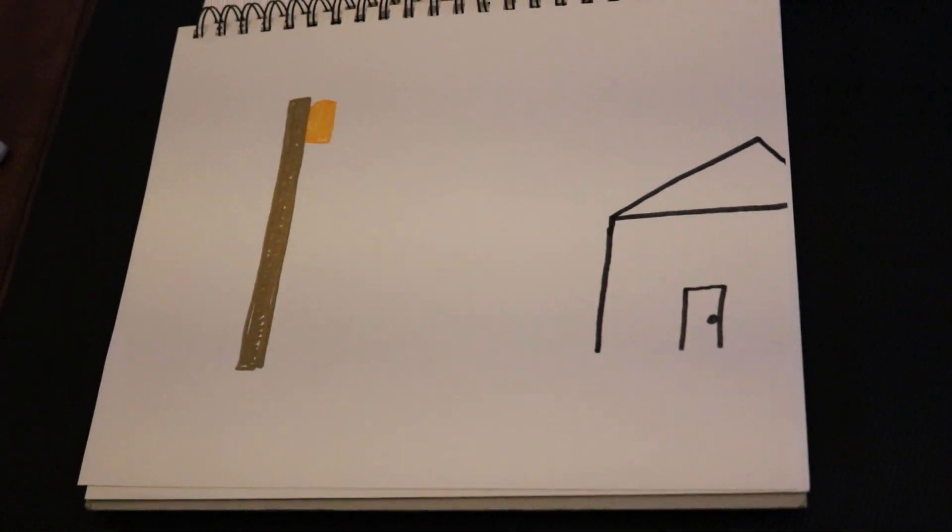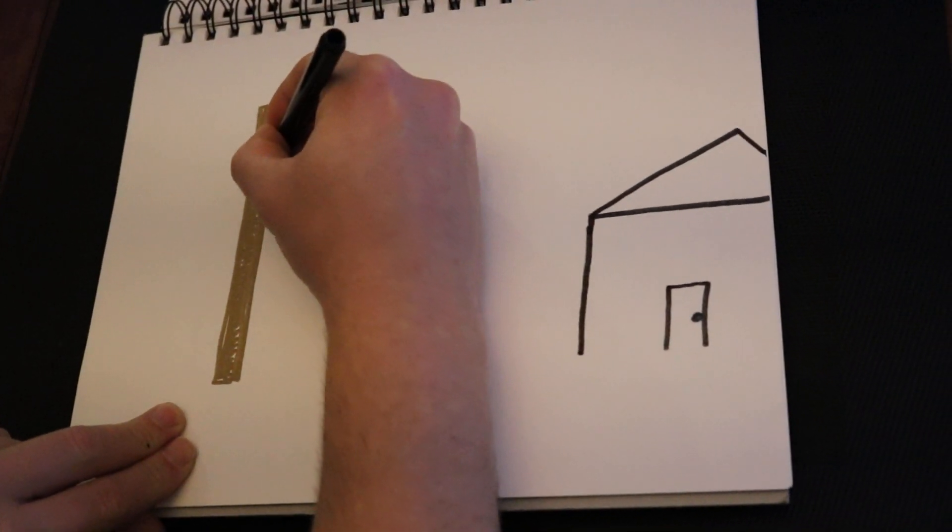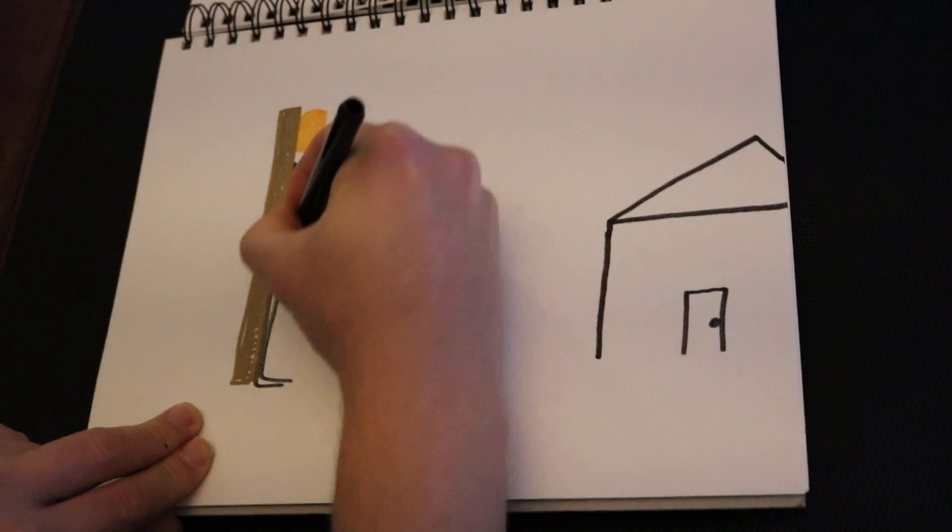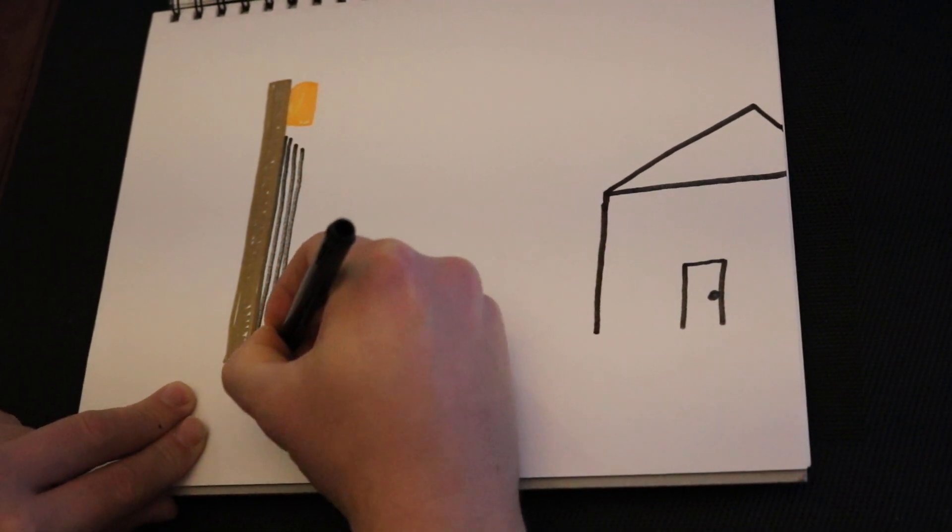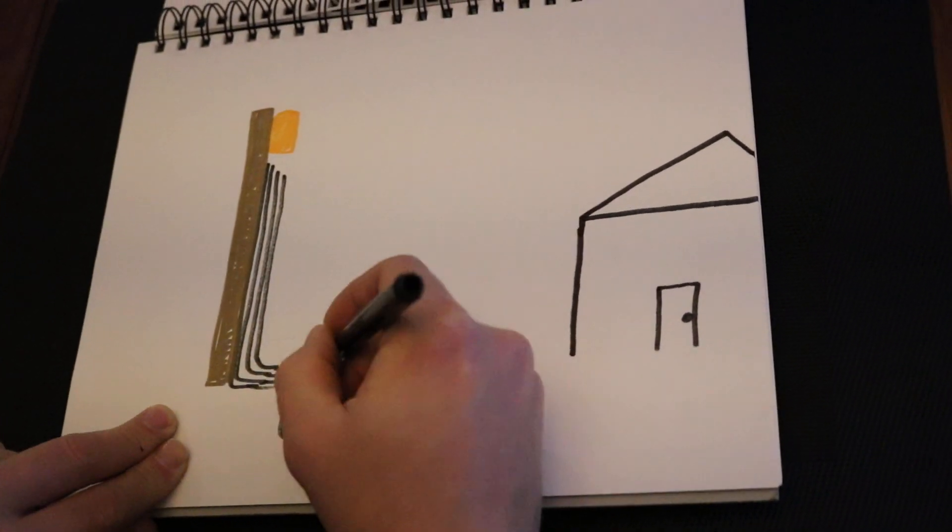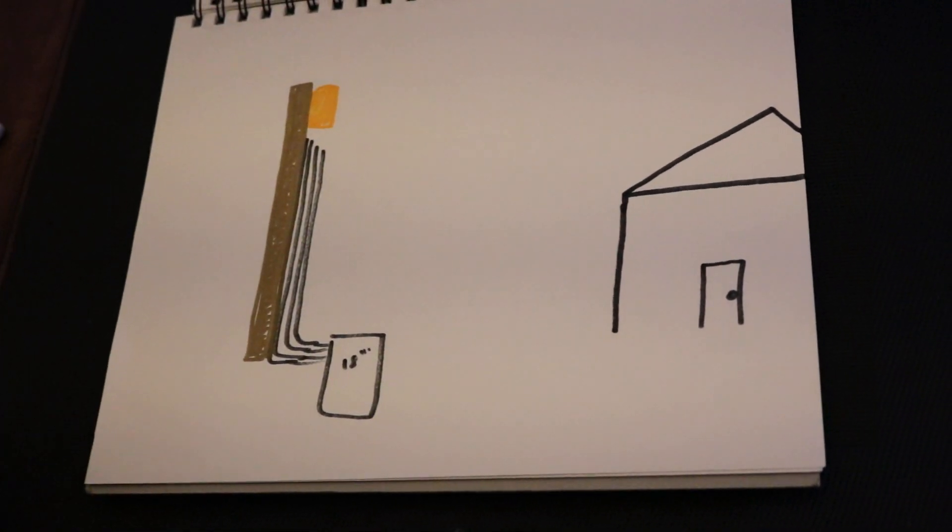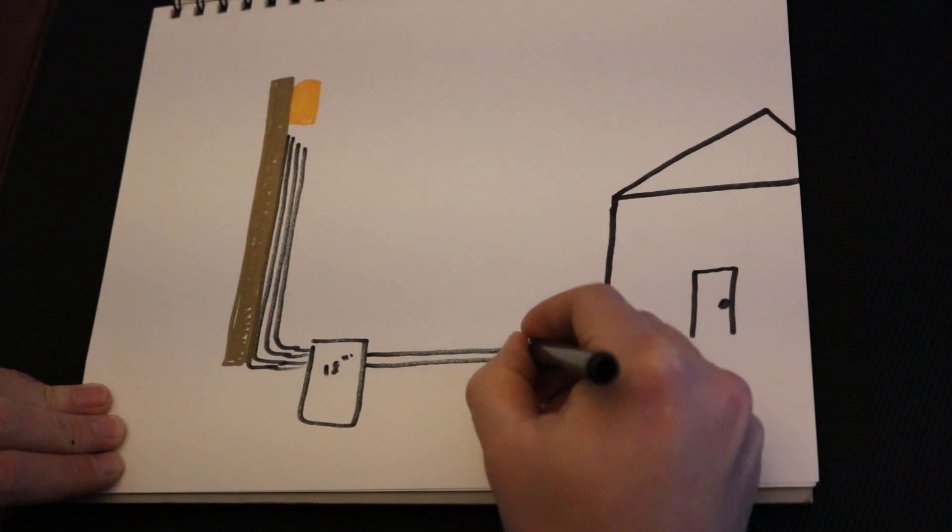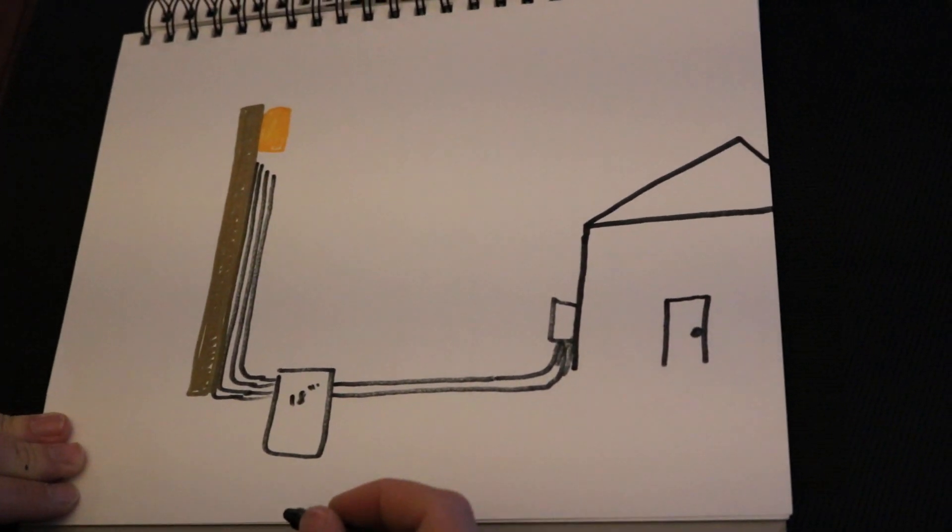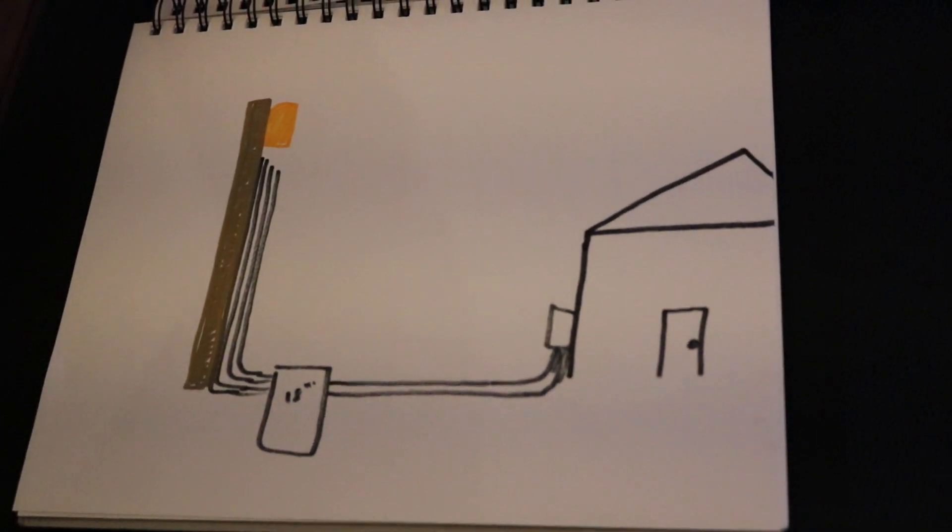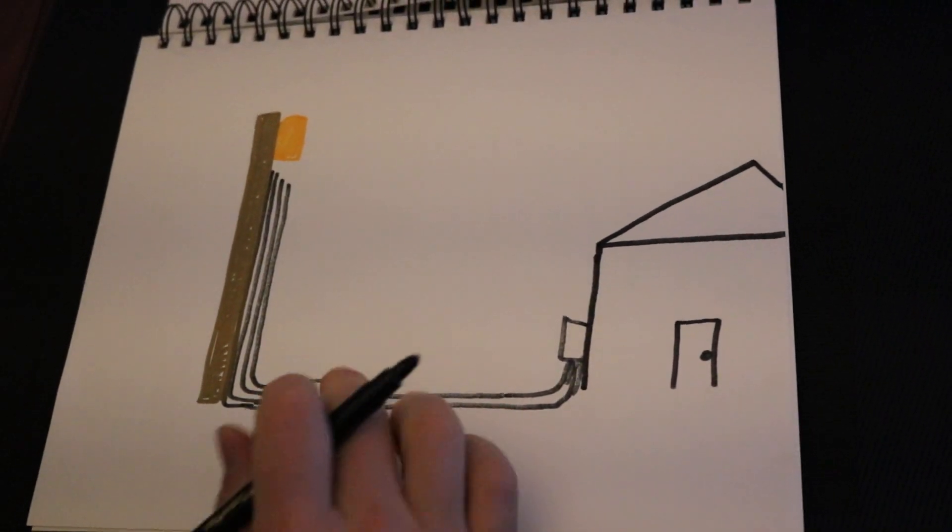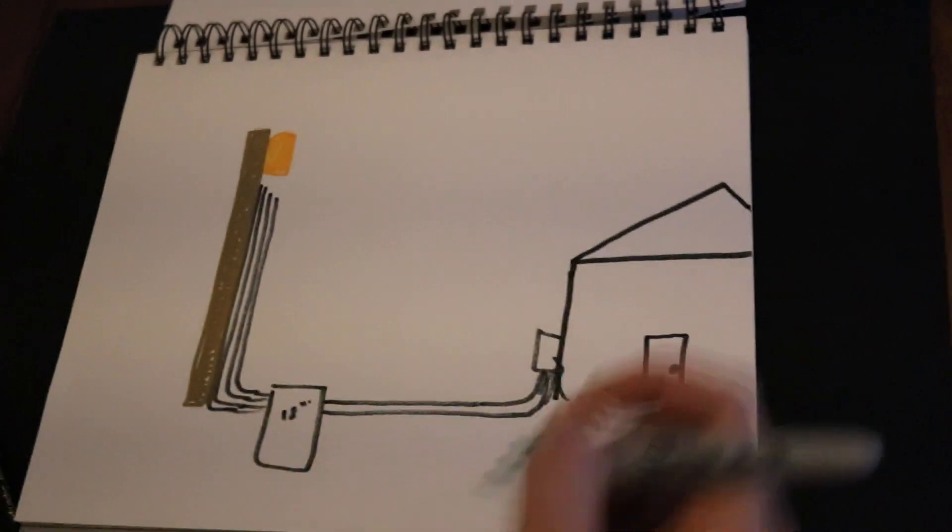Last but not least we're going to do a secondary riser. And this is where you have a pole, a conduit going up the pole in the transformer. Austin Energy requires us to have two conduits, and it goes to a manhole. There will be a designer that works on the project with you and they'll tell you the manhole, but usually it's an 18 inch manhole. And from there, it just goes underground to your electrical service. It's just going to be your AB and neutral going from here to there. Then your ground wire will be a Ufer ground usually or could be ground rods.